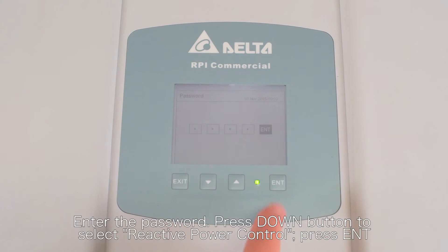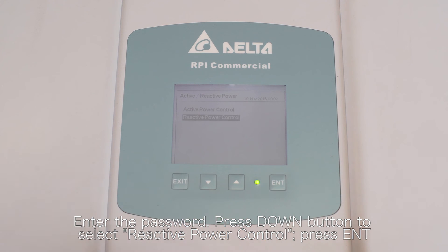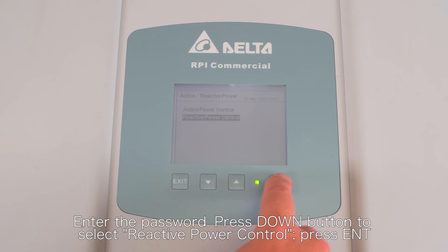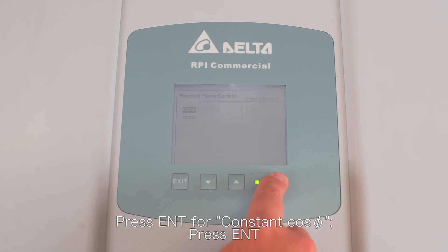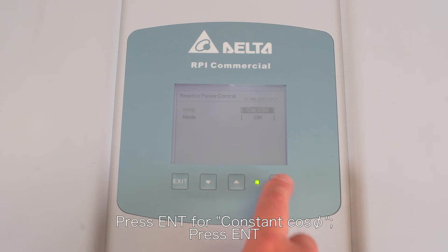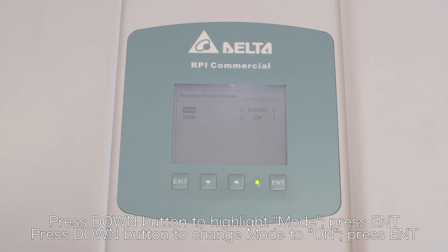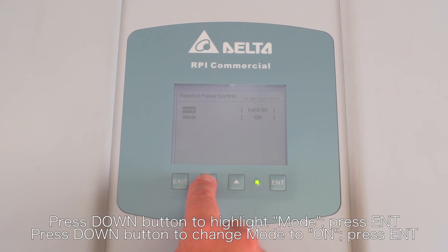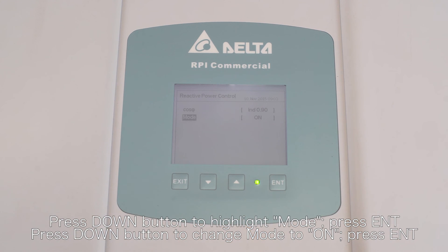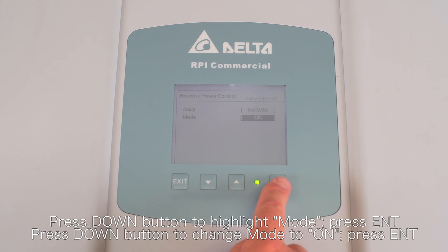Enter the password. Press the down button to select reactive power control and press enter. Press enter for constant cos phi, then press enter again. Press the down button to scroll through the options and select the appropriate setting by pressing enter. Press the down button to highlight mode and press enter. Press the down button to change mode to on, then press enter.